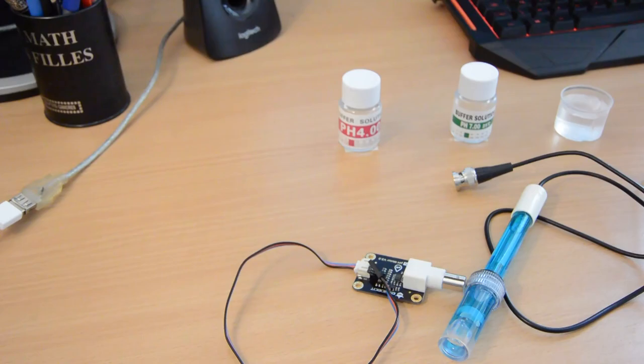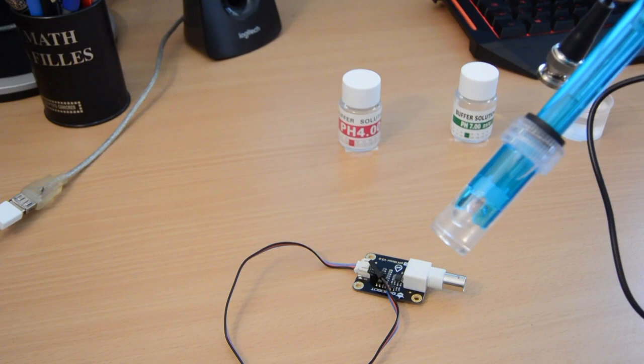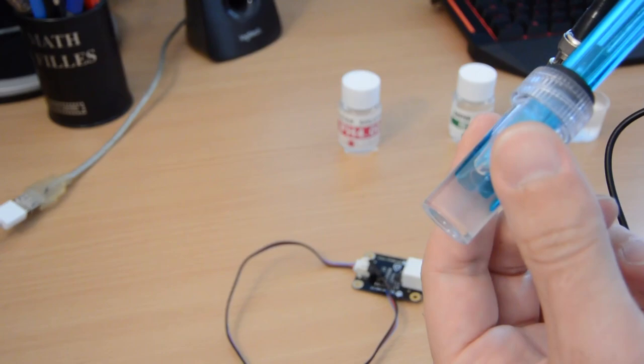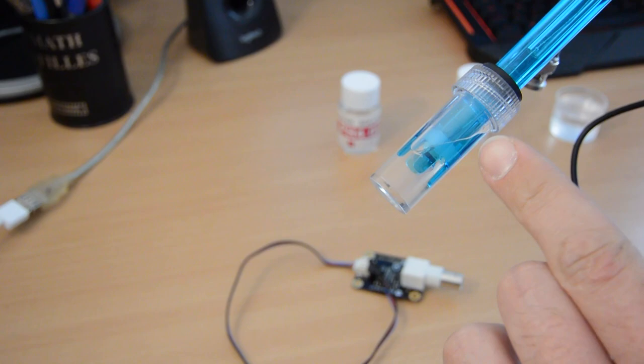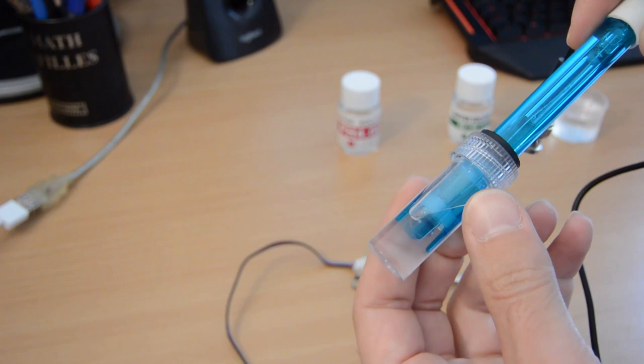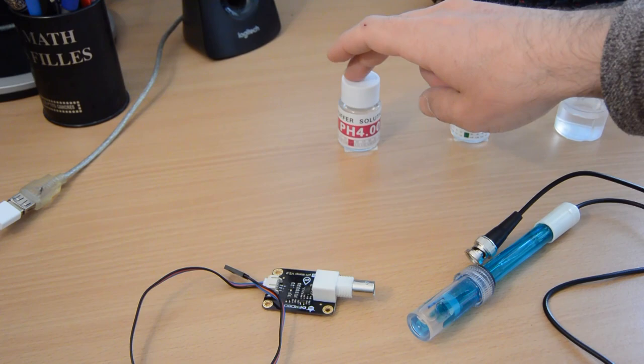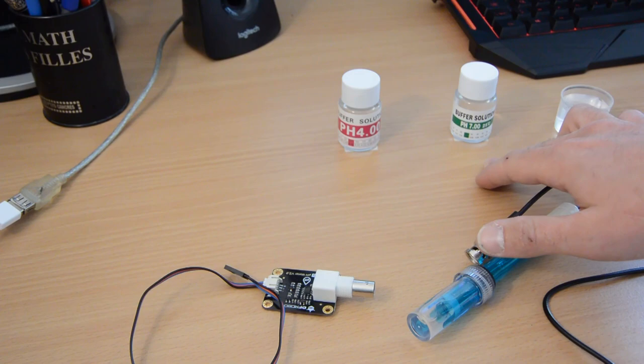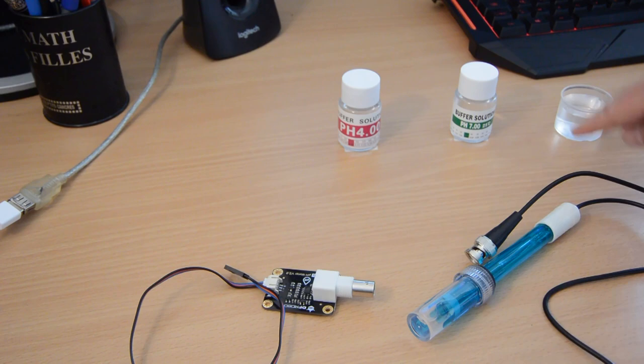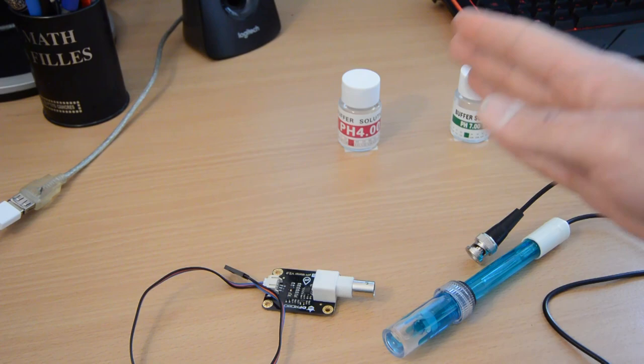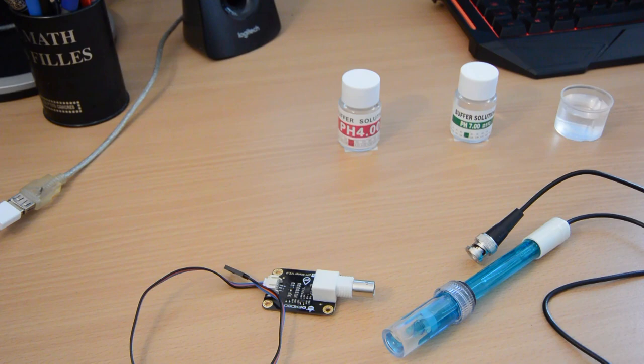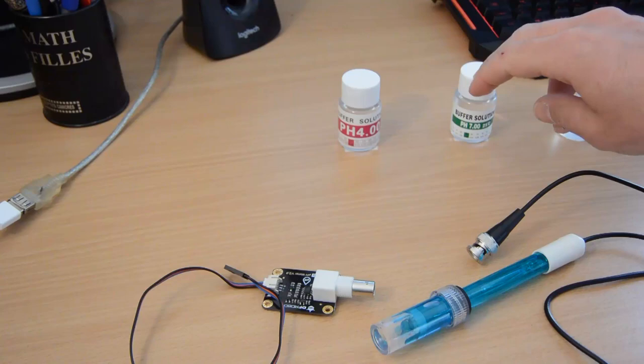So you've got your typical kit. You receive this box. And this box contains the pH sensor, which is within a solution right here. It's very important that that probe is always with this solution and that has to never be dry. You never want it to be dry because it will kill the probe and it will be useless. You have your pH circuit version 2. You've got your two standard calibration solutions. One is pH 4, one is pH 7. And what I've added here is a cleaning solution for the pH probe.